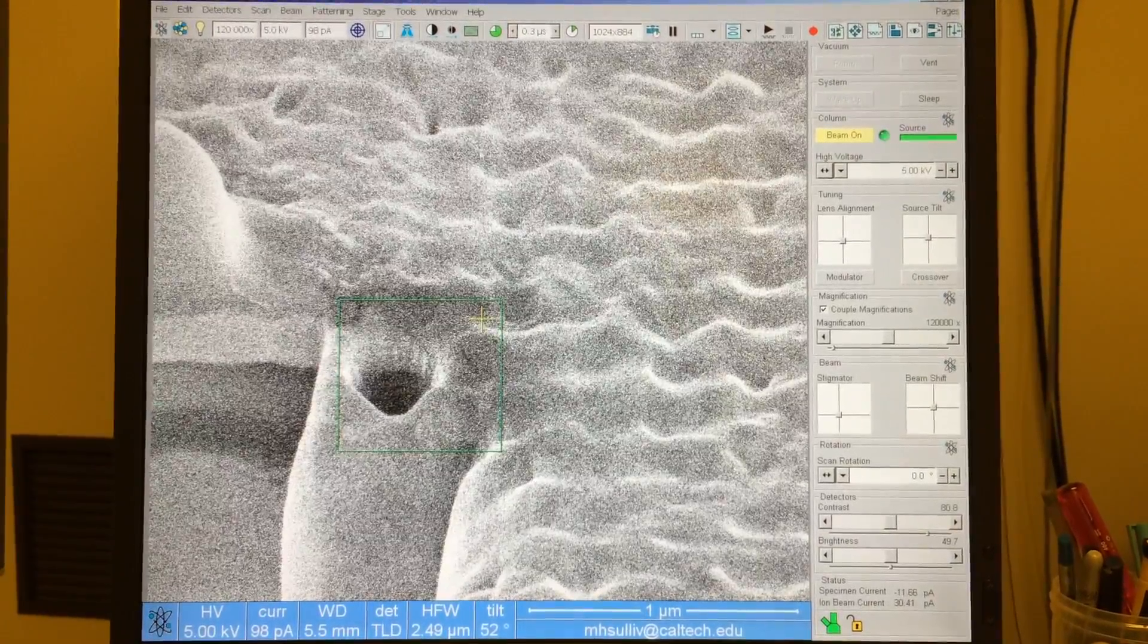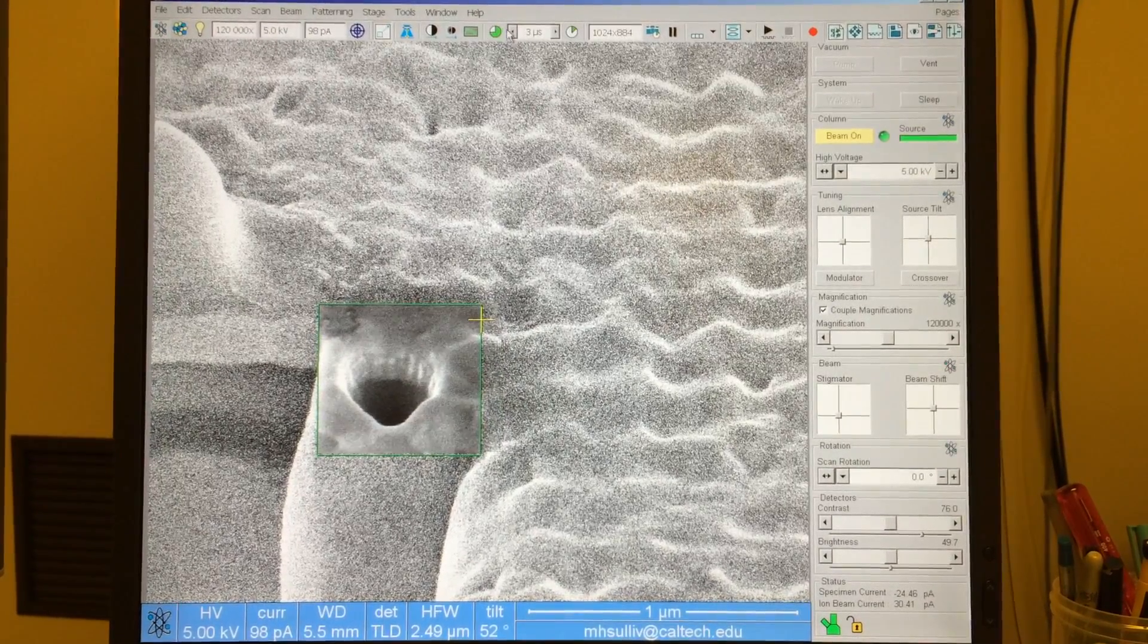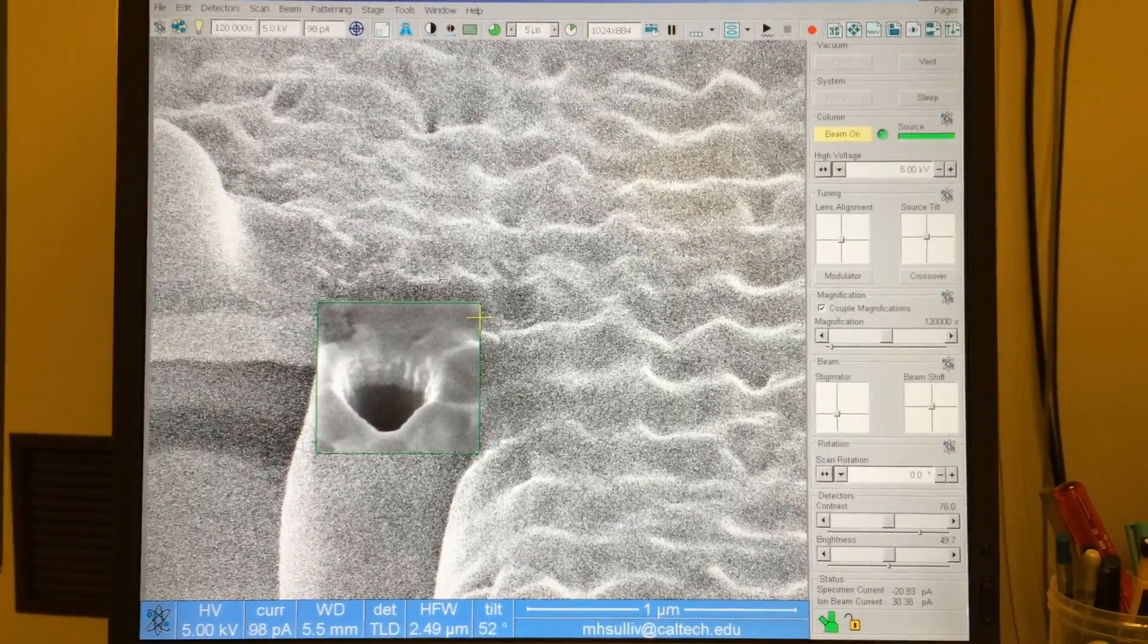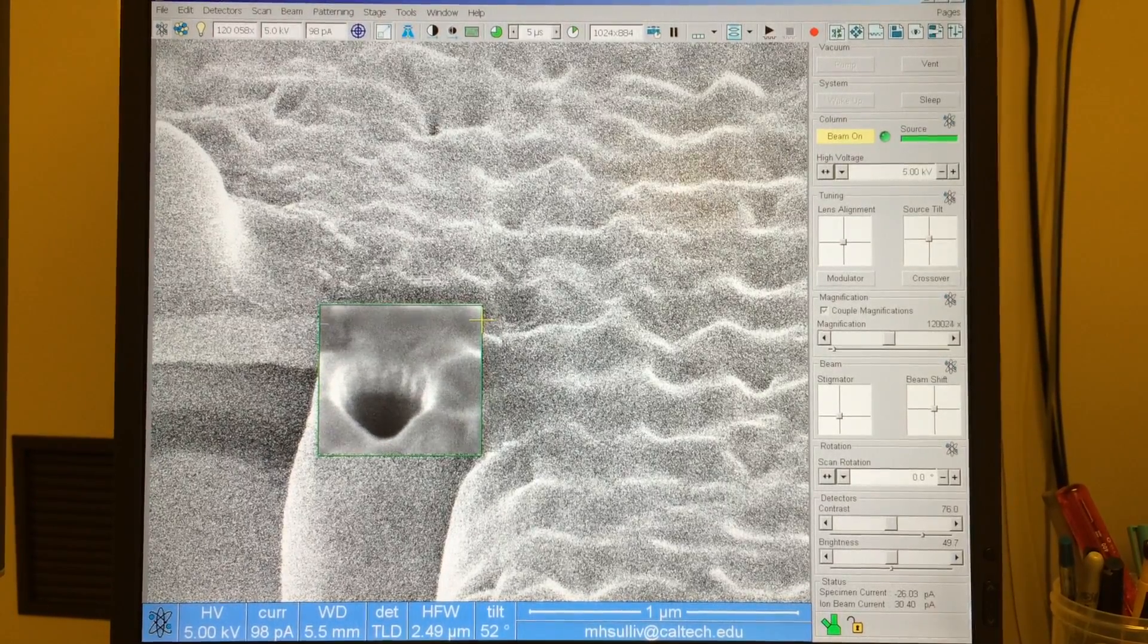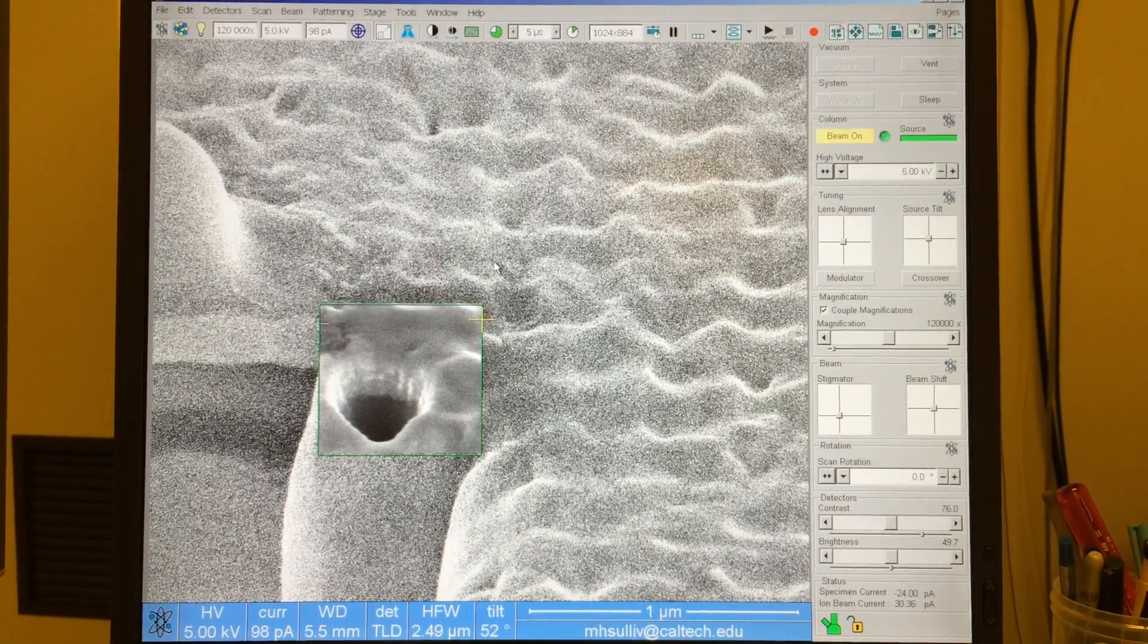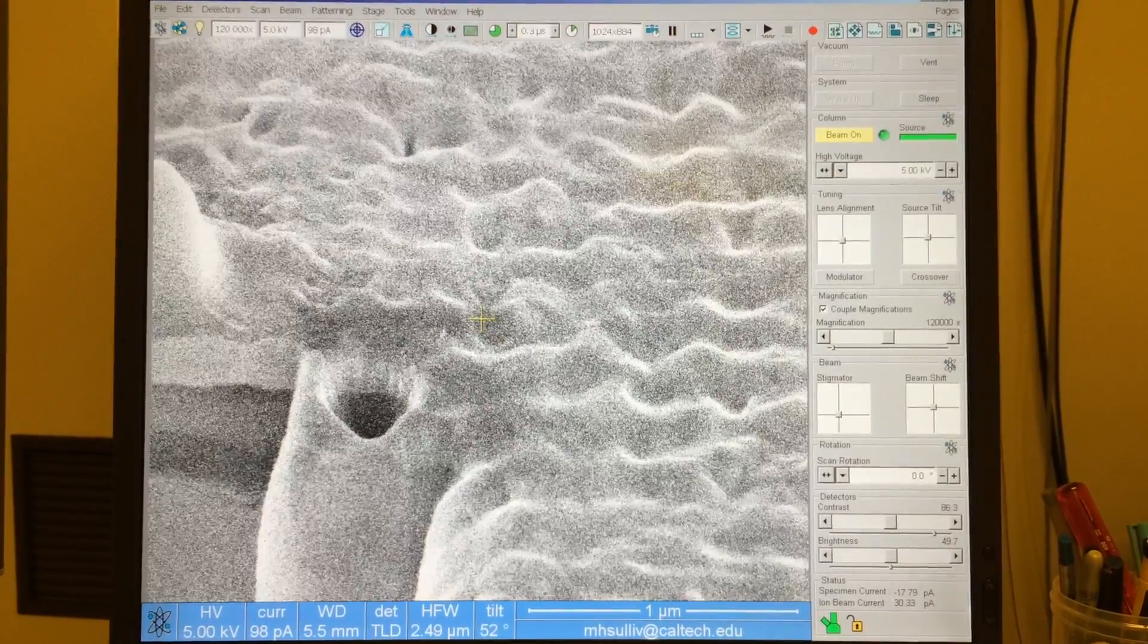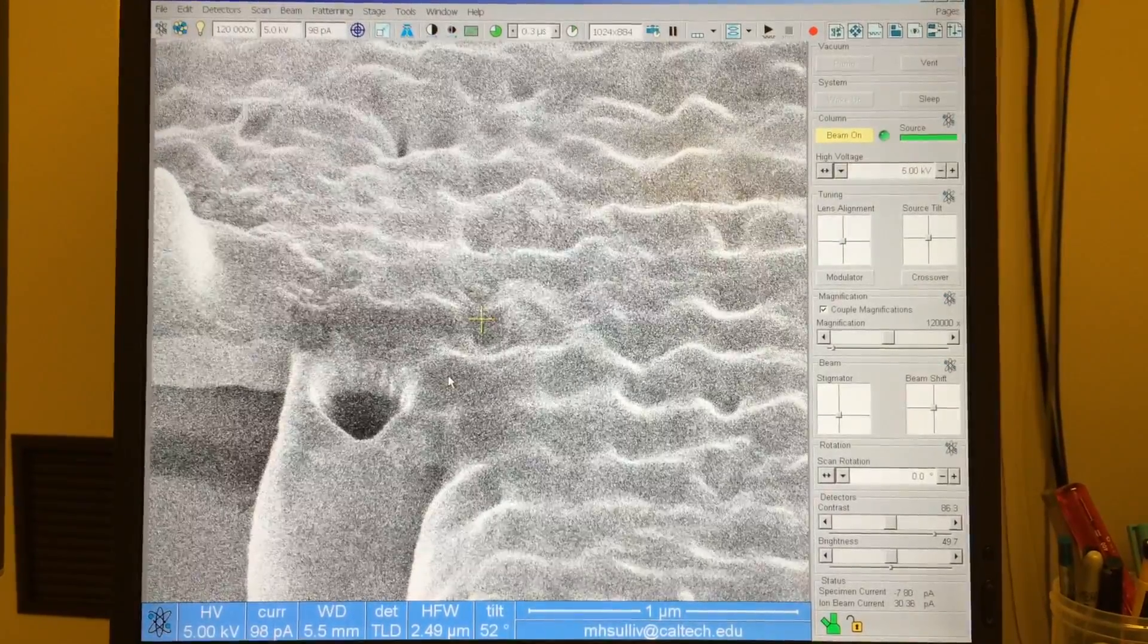So now that I've done the lens alignment, I should go back and adjust the focus and astigmatism again. I'll go to something like 3 or 5 microsecond dwell time so I can see that texture pretty clearly. I'll change my focus and my astigmatism. And with that, I have a first approximation of my alignment that I can use and then perfect in the next video using the alignment rectangle technique.